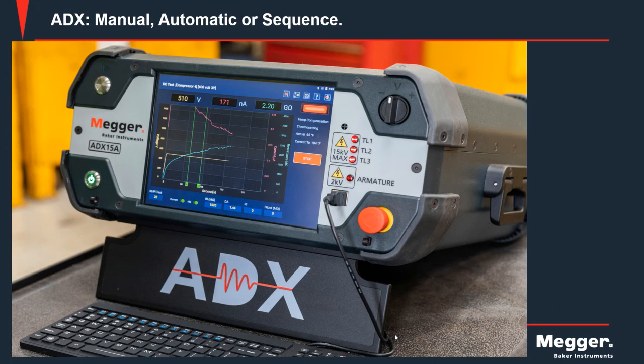Now, as you can see, the unit has got a nice digital display, and we can go in there, and if you've got an asset number or a job number for this particular motor, we can simply say 1, 2, 3, 4, and then any information that we record is saved to that serial number or that asset number. So it's really easy to manage. It can be as simple as just push the button and test, or we can set up routes, and just like vibration analysis, if you've seen one of their systems, they have a list of all the plant, and then we just go through and we can test each one in a round robin style test sequence.